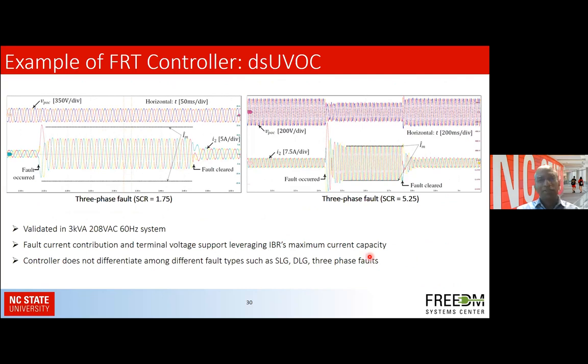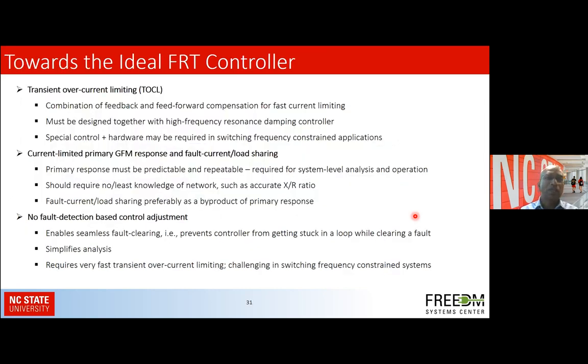So again, I'm running out of time, so I'll very quickly go over these results of the three-phase faults. Again, what is shown here is it's being able to ride through and limiting the current within the maximum current capacity for the IBR. And then again, two conditions of two different short circuit ratios are shown over here. So ideally, for those of us working on these fault ride-through controllers, how do we go towards the ideal fault ride-through controller for GFM type IBR resources?